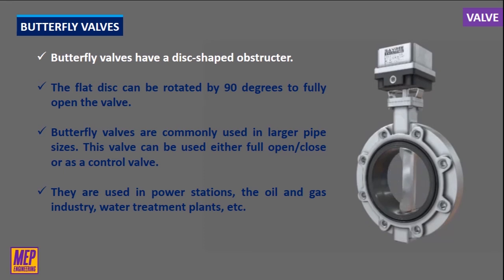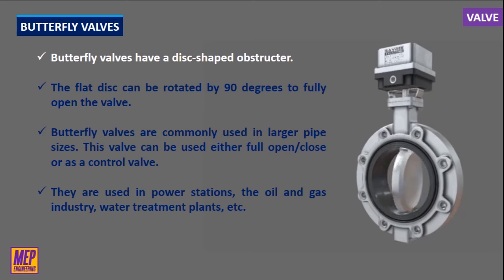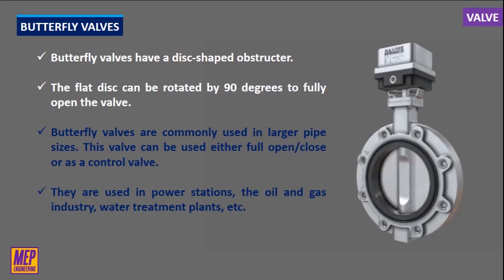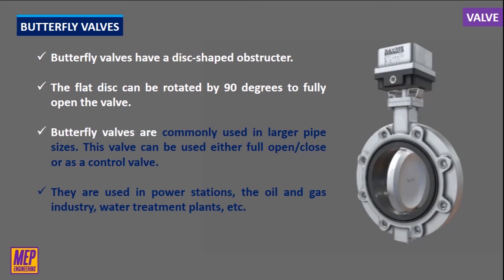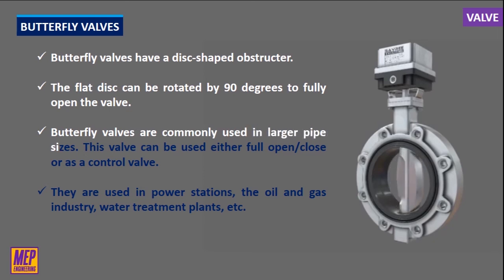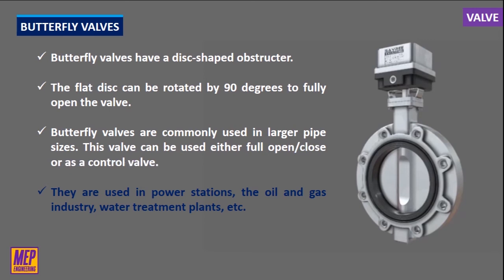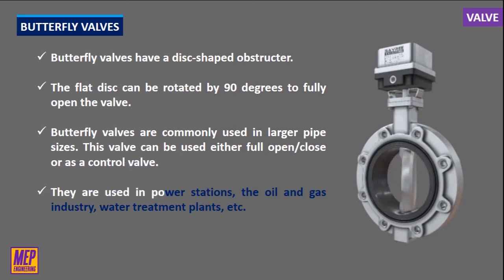Butterfly valves have a disc-shaped obstructor. They are the most simple but versatile valve in the industry. They have a single seal ring that acts as a seal between the valve body and disc, as well as between the pipe flanges and valve body. The flat disc can be rotated 90 degrees to fully open the valve. When the disc is perpendicular to the direction of flow, the flow is stopped; when rotated 90 degrees, the flow goes through the valve. Butterfly valves are commonly used in larger pipe sizes.